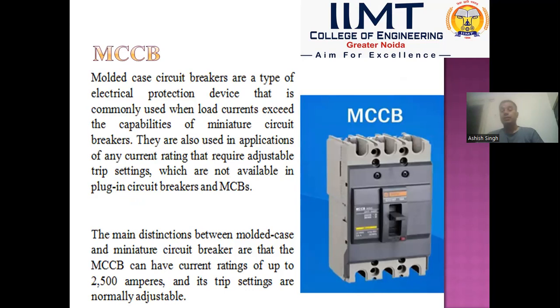Then another important switching device that is used in LT switchgear is MCCB, that is molded case circuit breaker. In molded case circuit breaker, we generally use a MCB and arc splitting chamber. Molded case circuit breakers are a type of electrical protection device that is commonly used when load current exceeds the capability of miniature circuit breaker. They are also used in applications of any current rating that require adjustable trip setting.